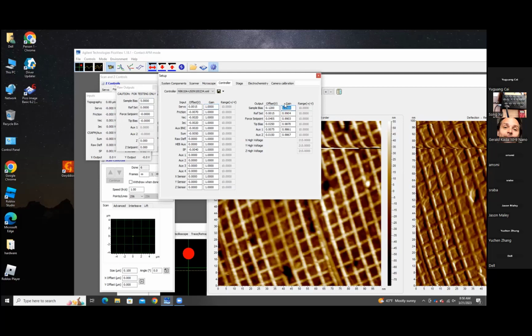We also know that 5 divided by anything larger than 5 is less than 1, right? So put in 0.9. That's the gain. And see how far it came down. I measured the sample bias again. It measured 4.56. So 0.9 is too low, 1 is too high. You can sit there and do the math if you want. It's not a problem. Or you can just do what you just did and find your medium, right? 0.95. Do I have to bring it up or down? Yes, 4.8. So we have to go up a little bit more.